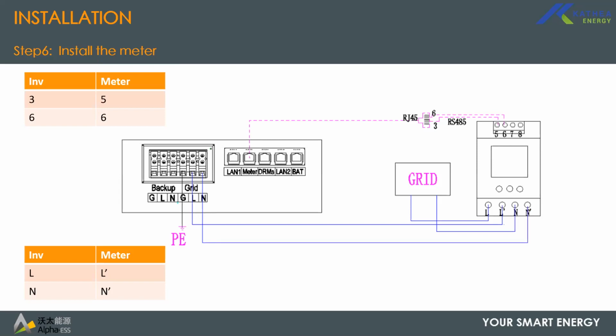And then the meter point. So this is the meter connection from your grid incomer. You get into L and N, and then you go out of the meter at L prime and N prime to your grid point on the inverter, which is the L and the N. And then you need to ground your G on the inverter. And then for the comms cable, you would need to wire an RJ45 to the meter point on the inverter. The meter comes with the RJ45 plug-in.